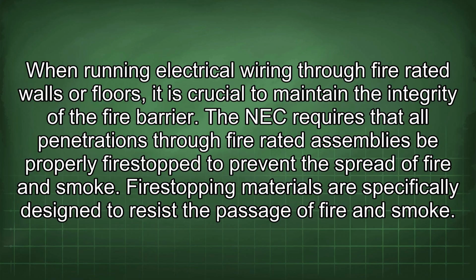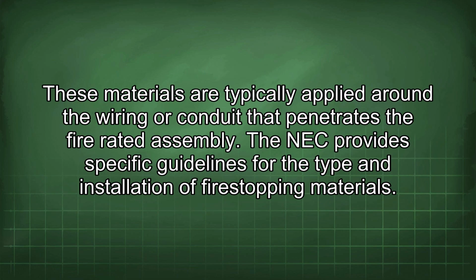When running electrical wiring through fire-rated walls or floors, it is crucial to maintain the integrity of the fire barrier. The NEC requires that all penetrations through fire-rated assemblies be properly fire-stopped to prevent the spread of fire and smoke. Fire-stopping materials are specifically designed to resist the passage of fire and smoke. These materials are typically applied around the wiring or conduit that penetrates the fire-rated assembly. The NEC provides specific guidelines for the type and installation of fire-stopping materials.